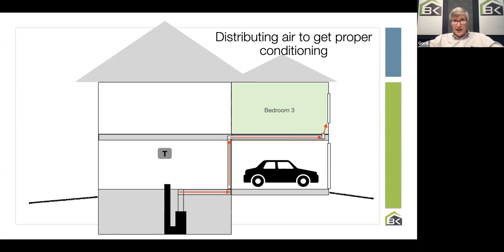We've designed for this longest run, designed a specific pressure in the furnace supply plenum to drive the air to that furthest point. And yet I often measure the pressure coming off the top of the furnace—it was designed at, say, 0.15, but it's only 0.08. It's half the pressure it was designed to be.